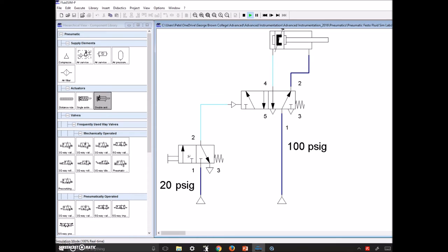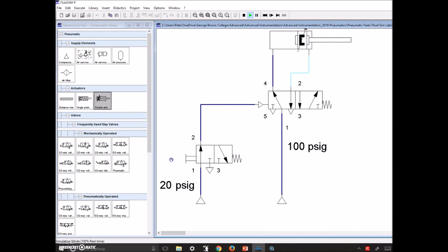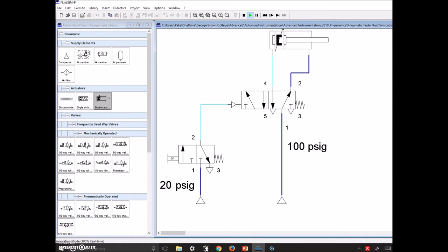Awesome little circuit here where we've got a smaller pressure controlling a larger pressure. With this one it doesn't hold because the spring is going to make the 5/2 go back to its rest state as soon as I let go of the push button. So once I press the push button it will extend; if I let it go it will retract. This is indirect control — this push button isn't directly controlling the double acting cylinder; it's controlling the 5/2, and the 5/2 is ultimately controlling the double acting cylinder.